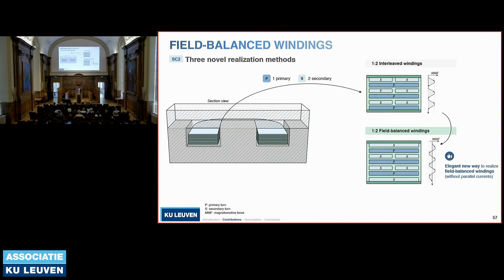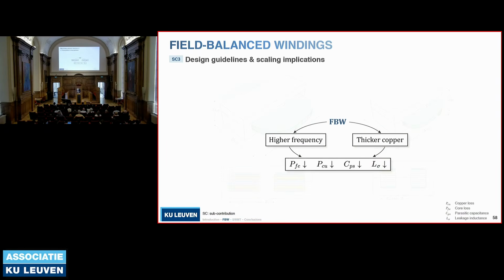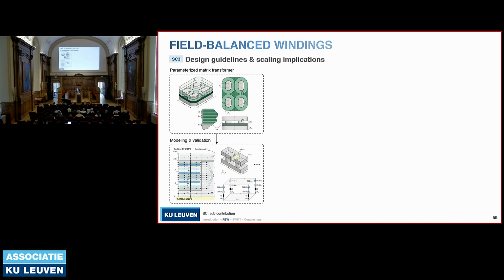Now that we understand how it works, the benefits are that we can run our transformers at high frequencies because of it, or use thicker copper since we're now using 2 surfaces of the copper. We can combine the two and find a system that improves all the relevant performance indicators of a transformer, from lower losses to lower volume, as well as lower parasitic effects such as parasitic capacitance and leakage inductance. To demonstrate these benefits, I do a full parameterization of a transformer, the one you see here.